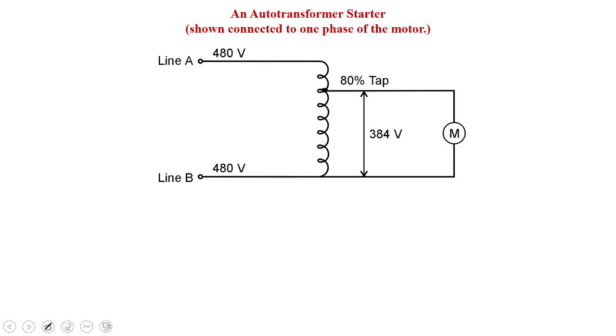In this case, we've got 480 volts coming in, and we're going to drop the voltage down to 80%, so down to 384 volts going to the motor. This motor itself is a 480 volt motor, but we're not going to give it the full 480 volts at the original startup. The reason is, if I reduce the voltage to the motor, I'm going to reduce the current to the motor. So here are our parameters.